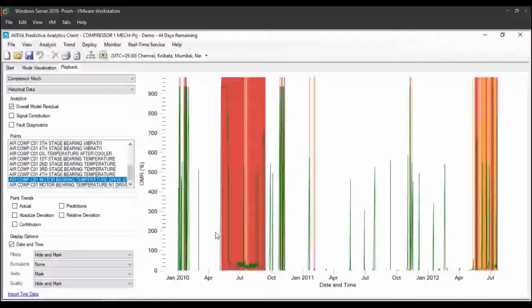Now, I saw another question with respect to how much data is required. In order to train the model, we want at least a year's worth of data, at around 15 minutes in frequency. The objective here is that if we take a raw year's worth of data, there will be some data that we'll exclude because it is unclean, as in it indicates an abnormal condition of the equipment. The other thing is we want to make sure that the accuracy of a profile is as high as possible. And as everyone of us knows, for any data-based algorithm to work, the more data there is, the better.